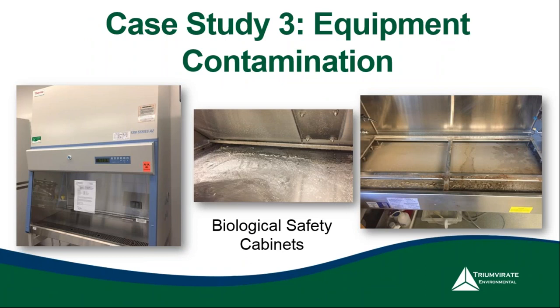We have some examples of problems we've experienced with equipment. At several locations, biological safety cabinets were recently disinfected with either vaporized hydrogen peroxide or chlorine dioxide and posted with NSF certifications for that disinfection process. After we were asked to review the spaces, we identified heavy organic loading and even debris underneath the work trays on these recently decontaminated biological safety cabinets. Although sterile, that heavy organic loading quickly supports contamination and dramatically reduces the equipment's effectiveness, degrading research quickly.